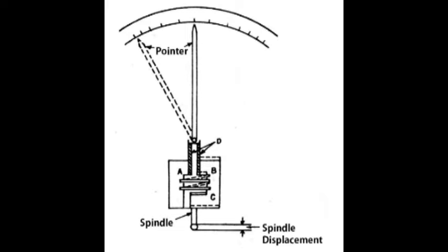A linear motion of the spindle moves the free block vertically, causing the vertical reed on the floating block to slide past the vertical reed on the fixed block. However, as the vertical reeds are joined at the upper end, instead of slipping, the movement causes both reeds to swing through an arc. The scale may be calibrated by means of a gauge block to indicate any deviation from an initial setting.